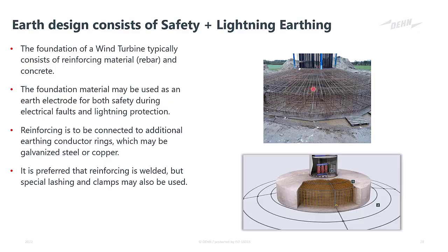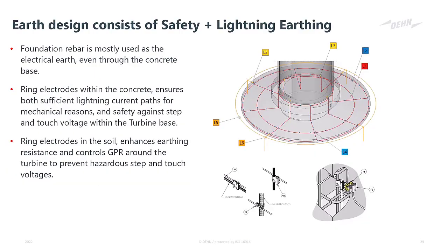Now, apart from that, you can also have ring conductors extending outside of the turbine that are connected within the turbine. This is required typically to control ground potential rise and avoid hazardous step and touch potentials, and it's more related to safety. However, it can also reduce the earthing resistance of the turbine earthing system as well. Now, this is just to elaborate again. You can see that the rebar is mostly used, and then these lightning conductors shown in red are inside the concrete connecting the rebar as well. This is a very basic representation, but you can see, for example, L1 is the red conductor, that's the lightning protection earthing conductor, and as indicated on the previous slide, you can use either galvanized steel or copper.